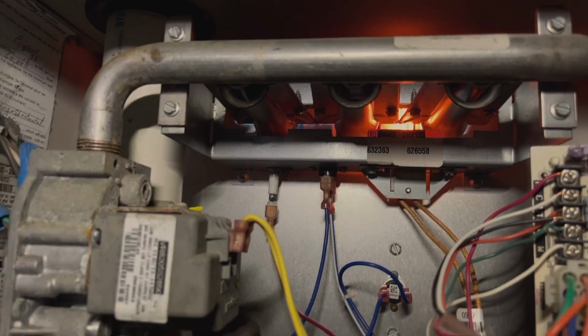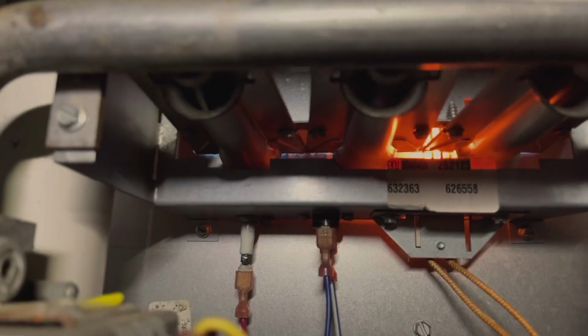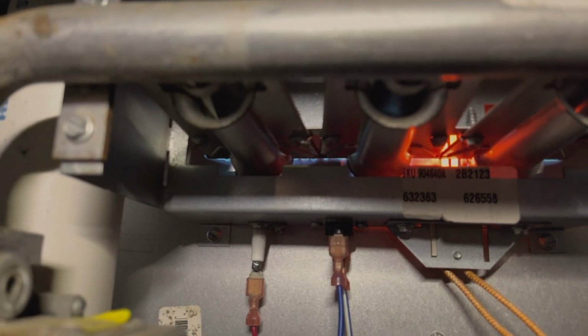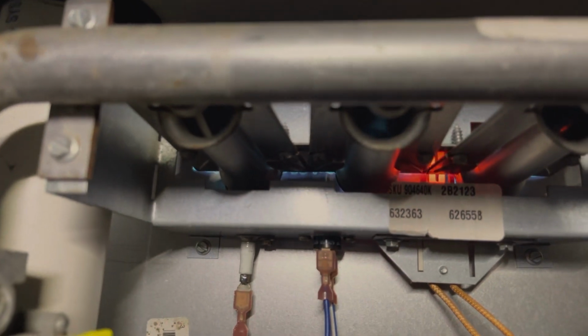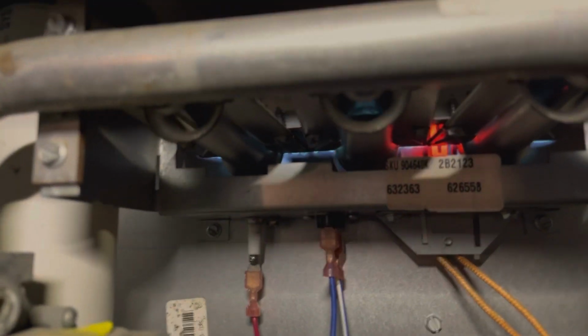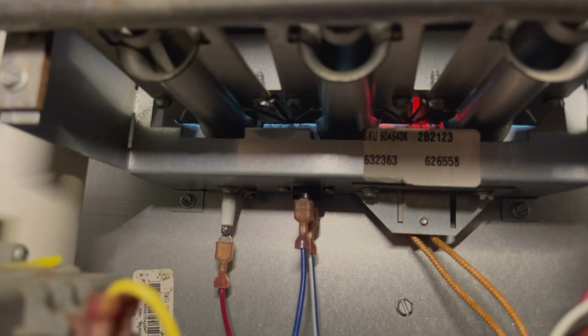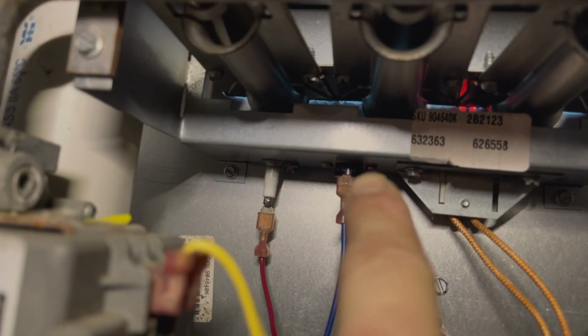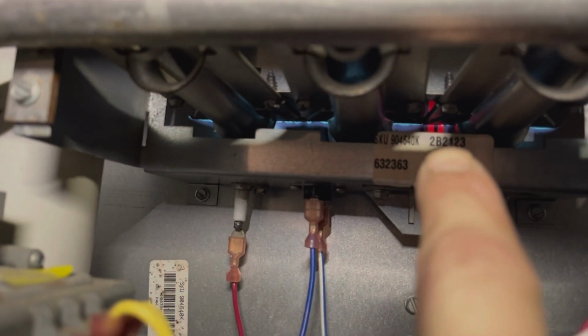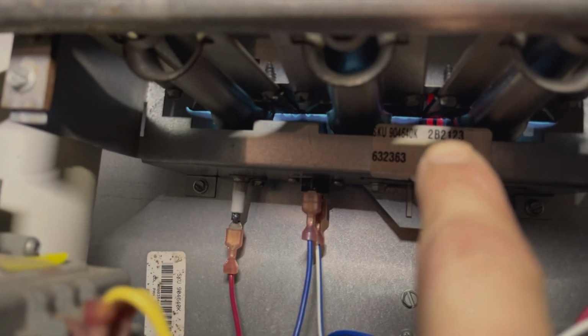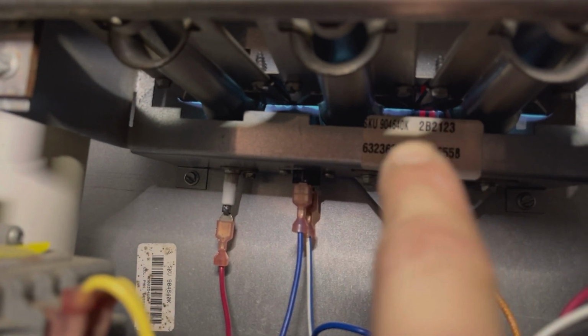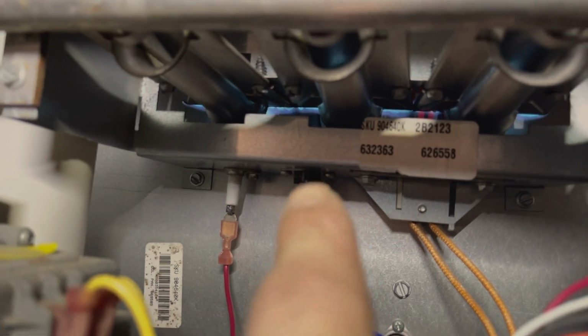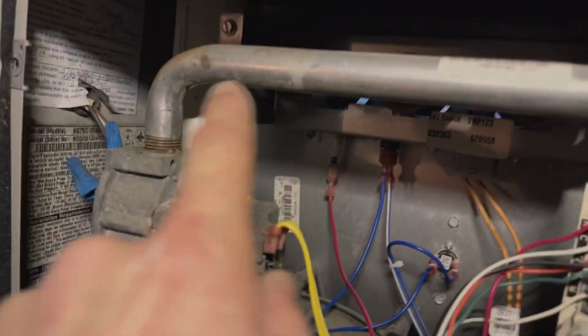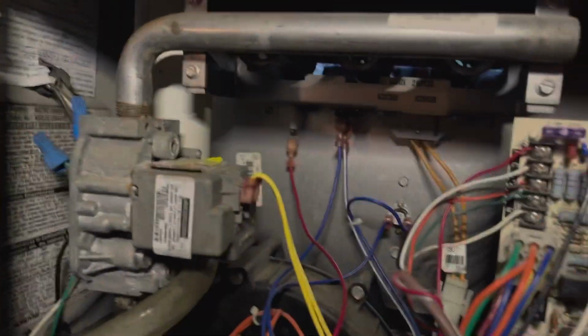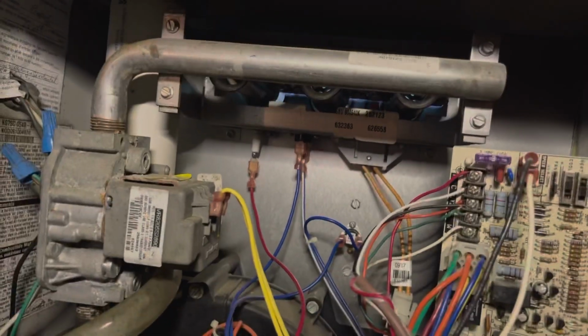Once it senses, there, now it turned on the gas and it lit. So you can hear it click on, and then the gas flows, and shortly after it lights. So my guess, if you guys know exactly, let me know, but I'm thinking actually that this limit switch is probably meant to sense the heat from the igniter. And once the igniter gets warm enough to light the propane, this senses it and then sends the signal back to the control board to then send the signal to the gas valve to turn on, because it will be lit and not build up and cause an explosion hazard.